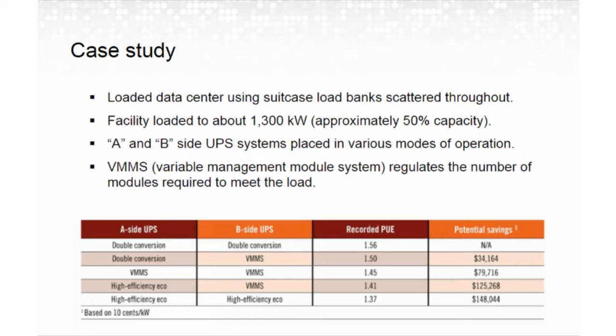And then we decided to put the UPS in eco mode. So we put one side in eco mode and one side in the variable management mode. Again, we saw another reduction to about $125,000, and then we put both systems into eco mode, and again, that was the lowest PUE recording, and it was about $150,000 of annual savings. This particular client, spending all the money on the UPS systems and the reliability, was not comfortable putting the UPSs in eco mode, so they've run their systems in the VMMS mode.